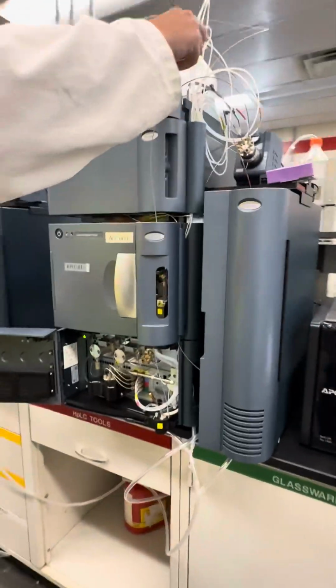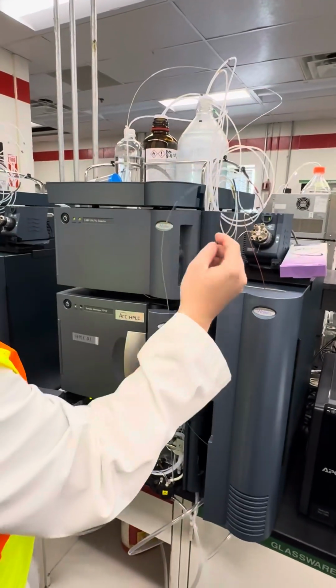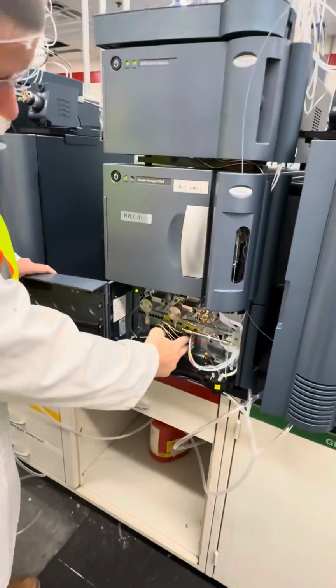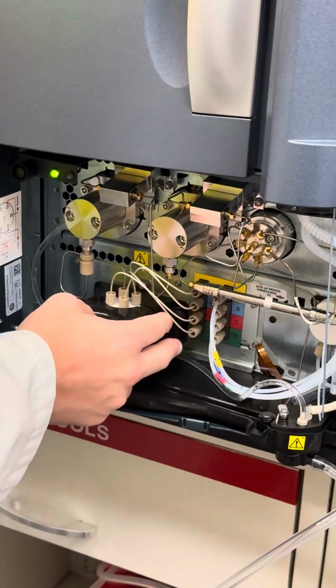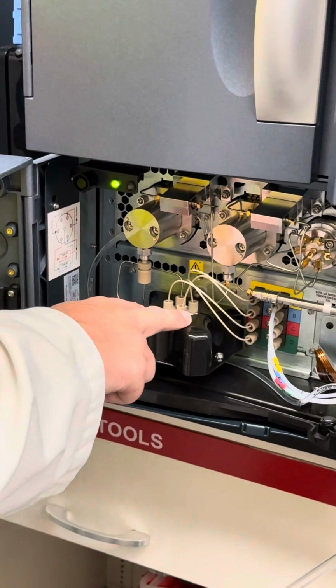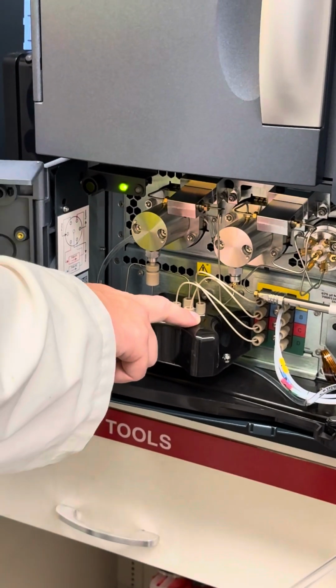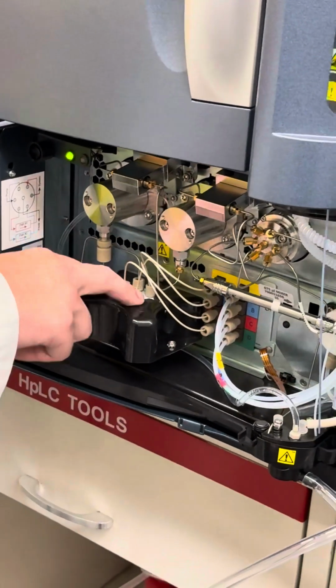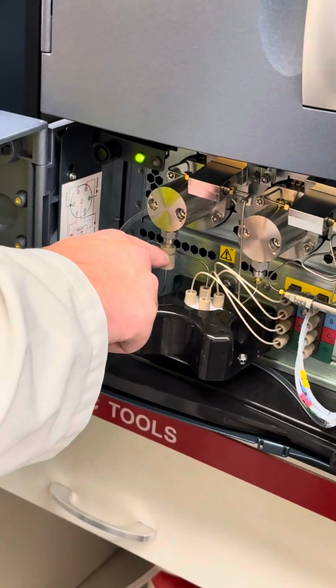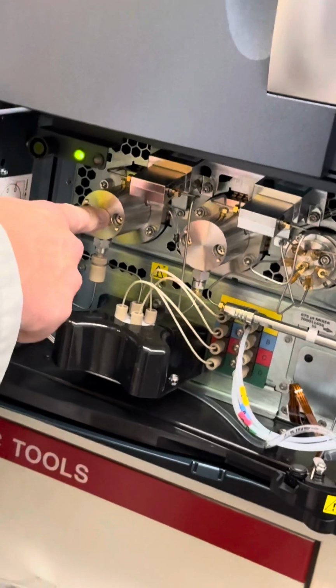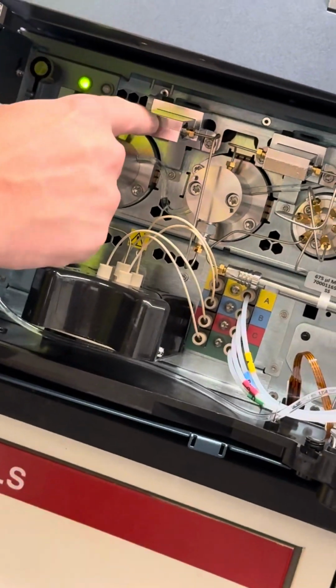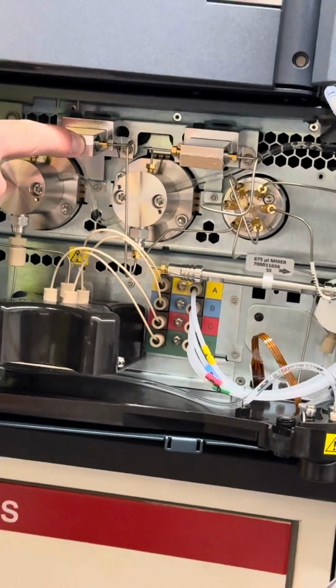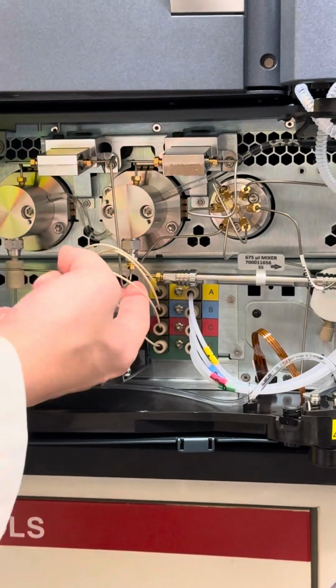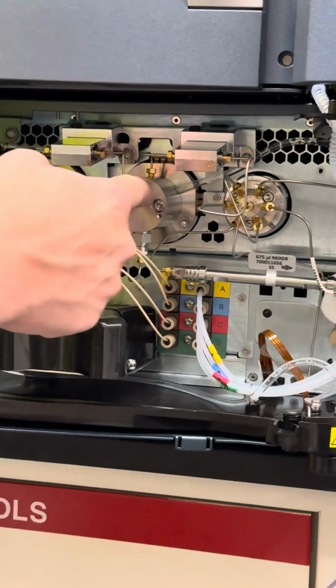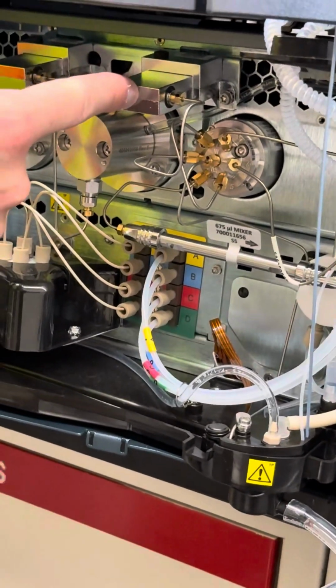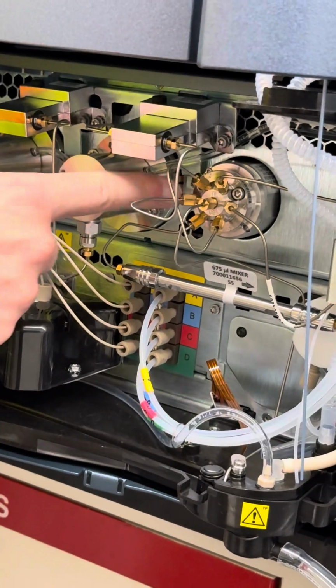So your solvents are going to run down here, flow all the way down here into your degasser chambers. They're going to run from your degasser chambers to your gradient proportioning valve. This is going to mix everything. So if you run at like A50 and B50%, this is where it's going to mix. It's going to go through here, through the inline filter, up through the check valve into the primary pump head. Okay, the primary pump head is going to go through this pressure transducer, which is where it measures that pressure, down into the accumulator check valve, into the accumulator pump head, and that's going to go to the accumulator pressure transducer and into the vent valve.